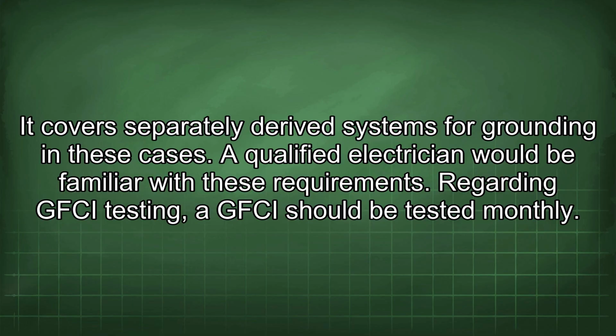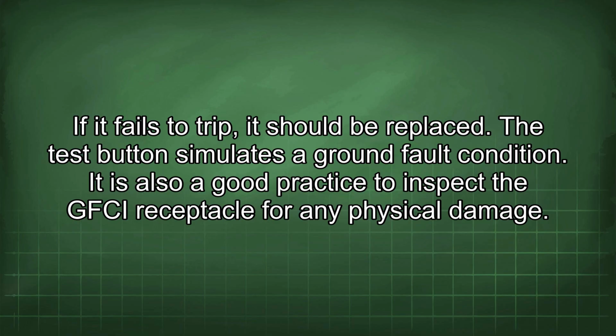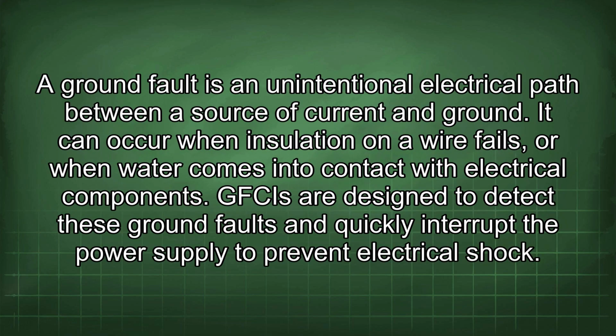Regarding GFCI testing, a GFCI should be tested monthly. If it fails to trip, it should be replaced. The test button simulates a ground fault condition. It is also a good practice to inspect the GFCI receptacle for any physical damage. A ground fault is an unintentional electrical path between a source of current and ground. It can occur when insulation on a wire fails or when water comes into contact with the electrical components. GFCIs are designed to detect these ground faults and quickly interrupt the power supply to prevent electrical shock.